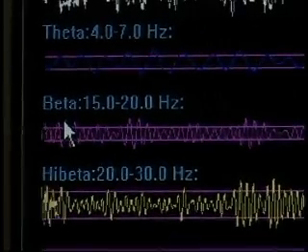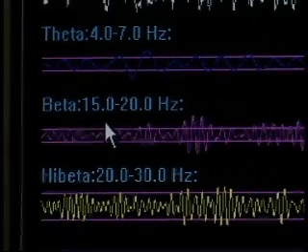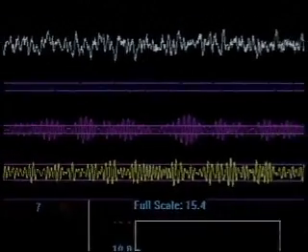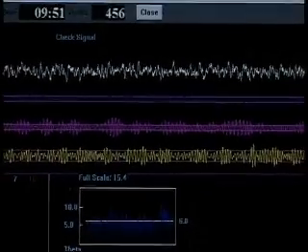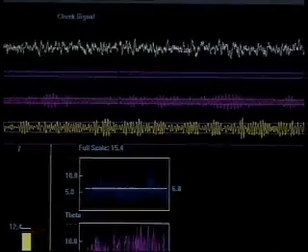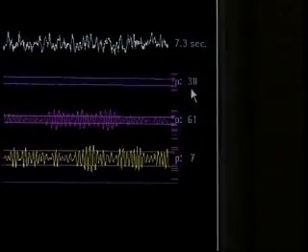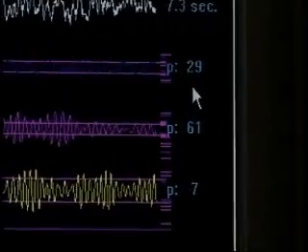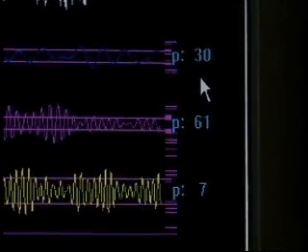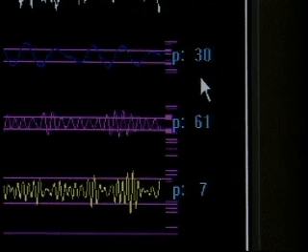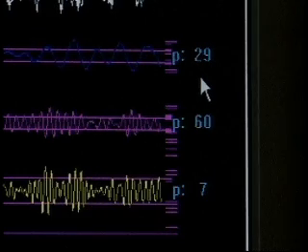I'm going to scroll completely to the right side of the screen, and we're going to see some numbers with a P colon. As we zoom in on those, these are telling you the current percent time over threshold numbers. And see how they fluctuate? These show where you are currently in percentage time over threshold, and it is exponentially damped.